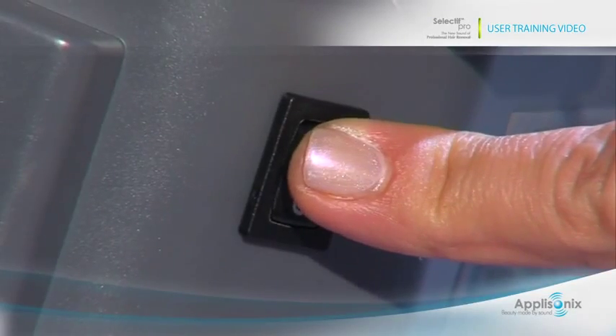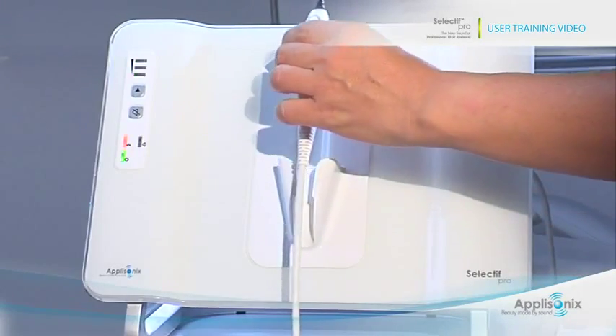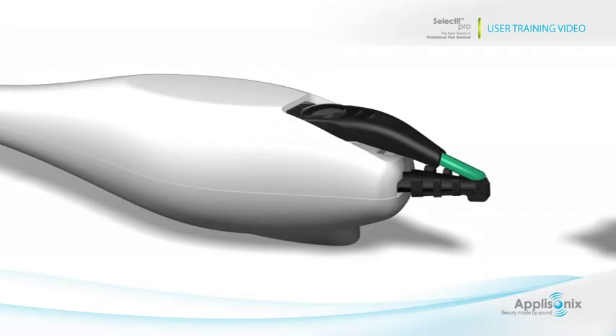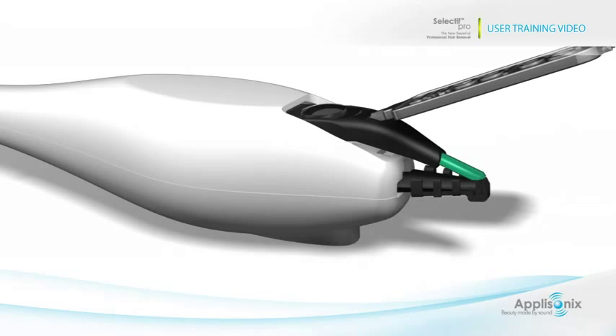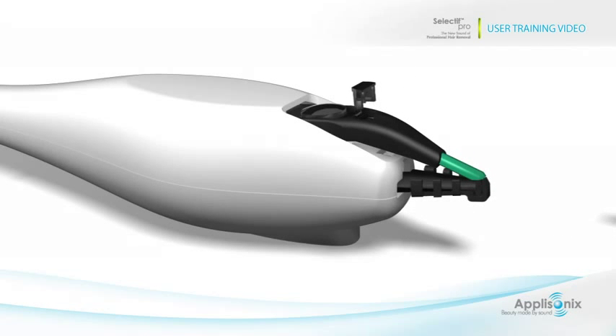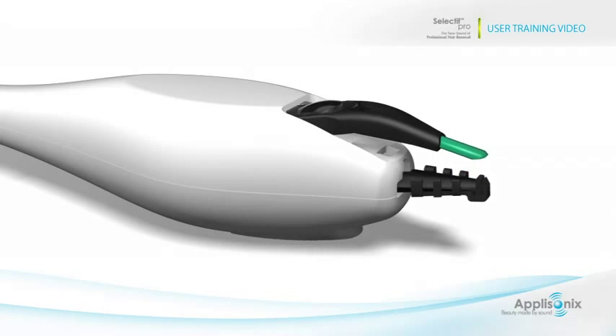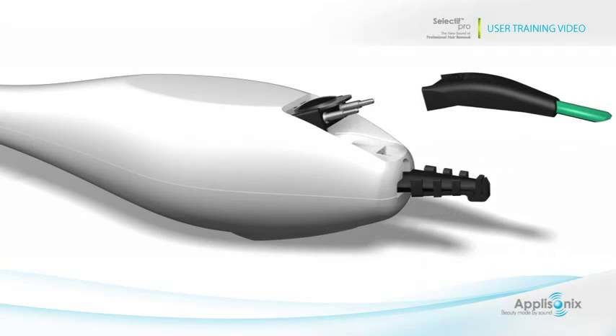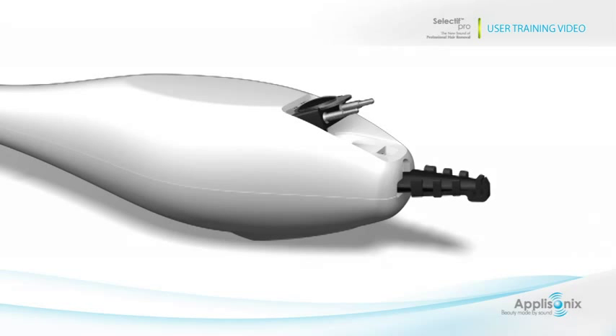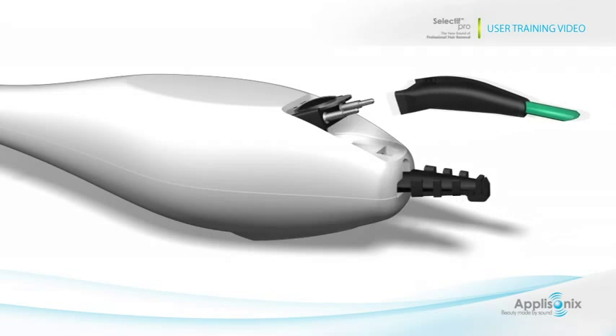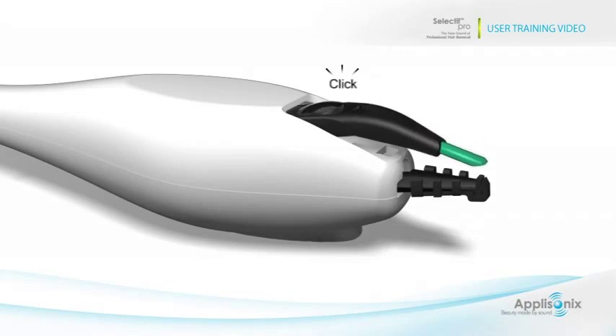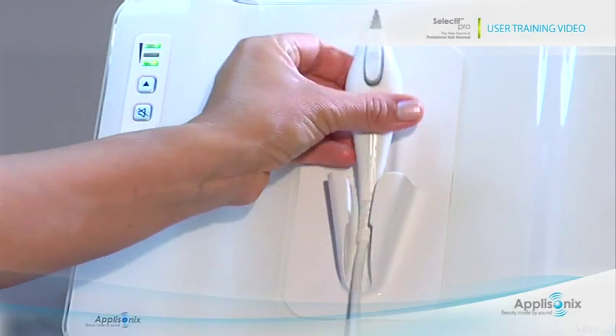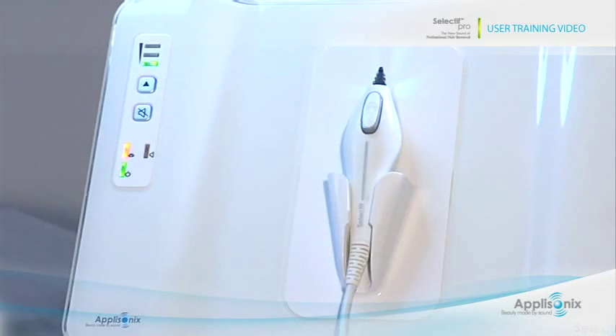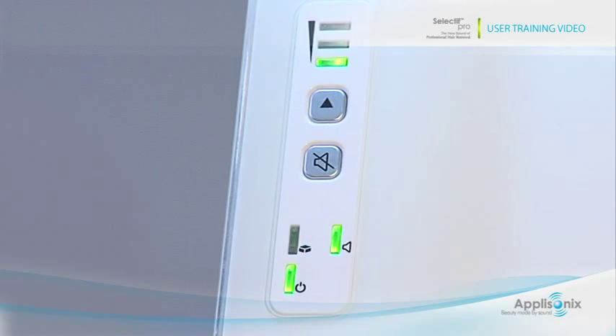Turn the power on, remove the probe from its holder and turn it upside down. Using the designated key, pull the safety cap out and remove the tip from the probe. Take a new gripping tip from the package and fit it into the probe until it is firmly secured. Place the probe back in its holder and wait while the system performs self-testing and calibration. The status LED will turn green when the system is ready for use.